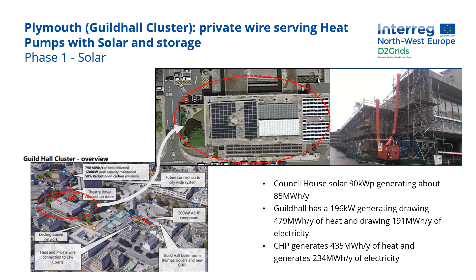Plymouth proceeded in 3 phases. The first consisted of installing photovoltaic systems across several buildings. Council House Solar: 90 kWp, generating about 85 megawatt-hours per year. Guildhall: 196 kilowatts, generating 479 megawatt-hours per year of heat and drawing 191 megawatt-hours per year of electricity. CHP generates 435 megawatt-hours per year of heat and 234 megawatt-hours per year of electricity. The aim was clear: to maximize local electricity production with storage to power heat pumps.